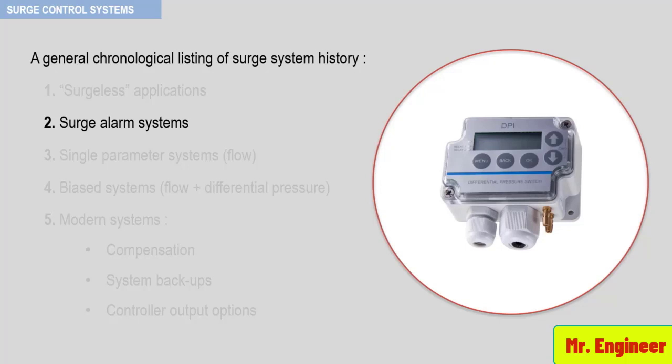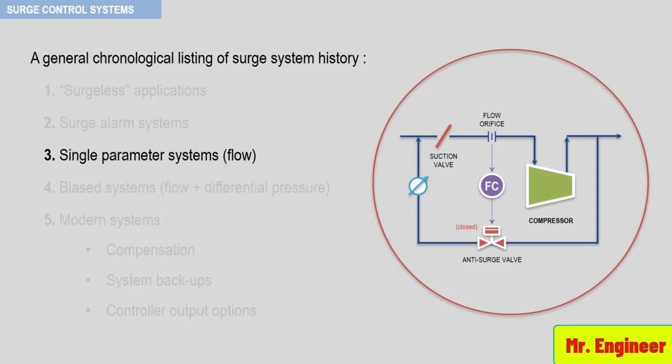The following figure shows a single parameter surge protection system. Single parameter surge systems have been employed extensively and very simply consists of a flow measuring device and an anti-surge valve as depicted here. These systems can work if properly sized and installed. However, it must be understood that a one parameter system will not be economical in a large area of operation. The result will be unnecessary recirculation of the gas and a loss of product revenue, as depicted here.